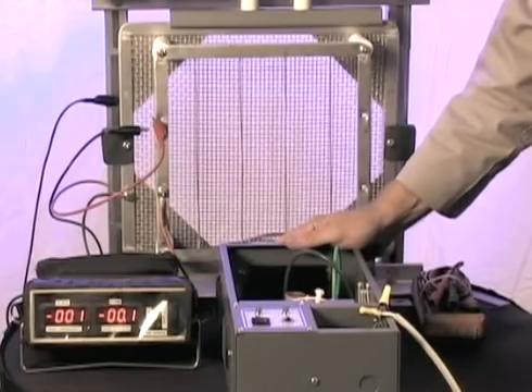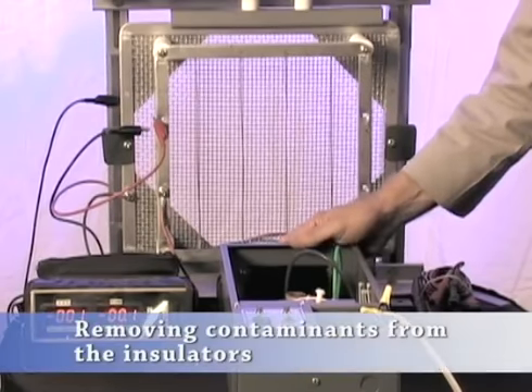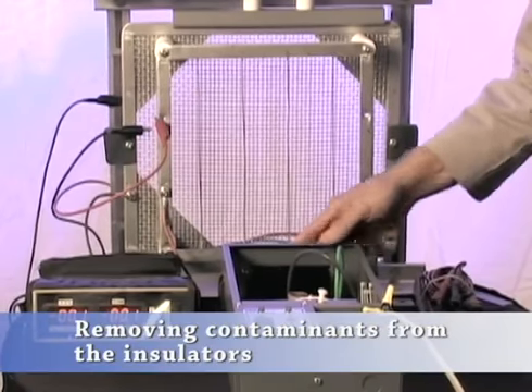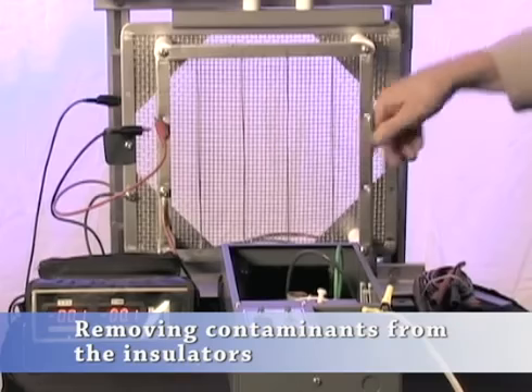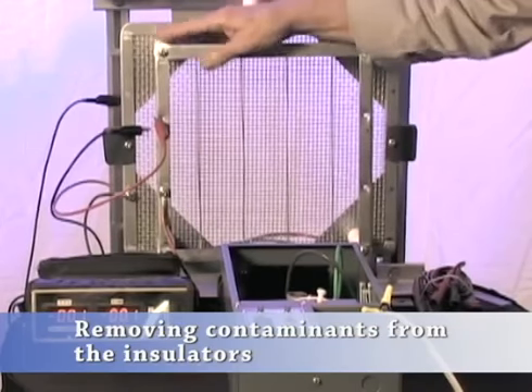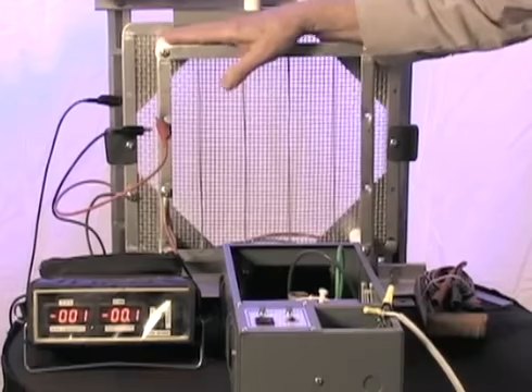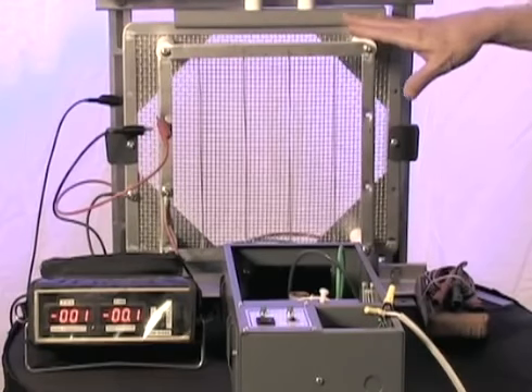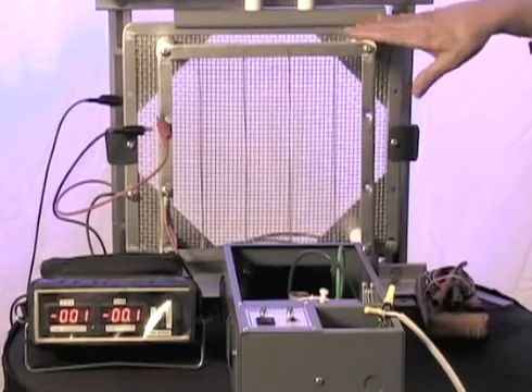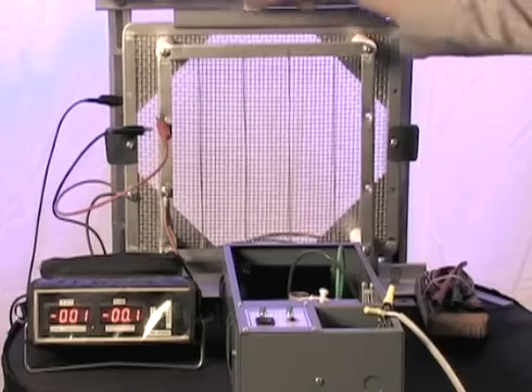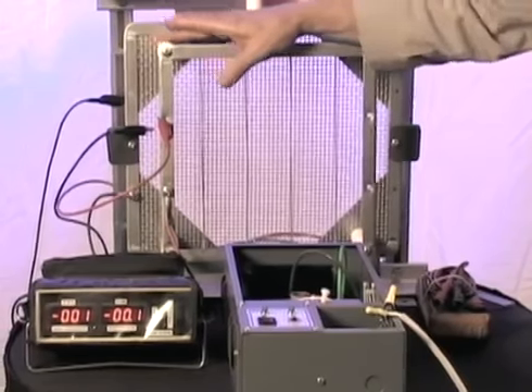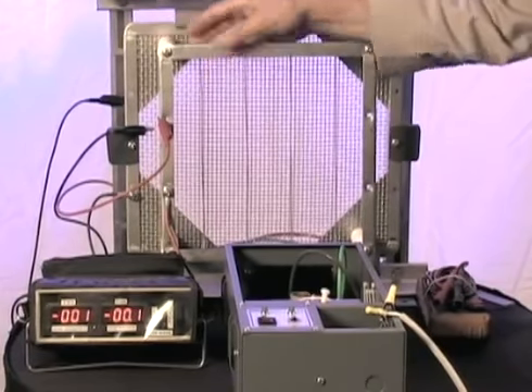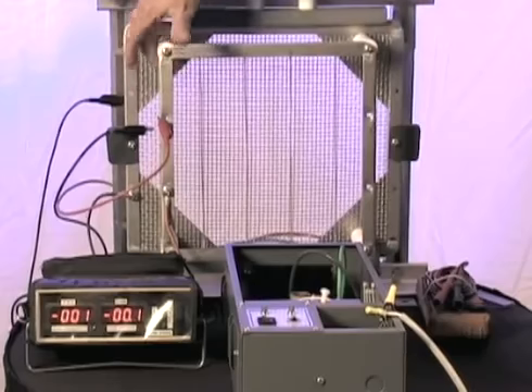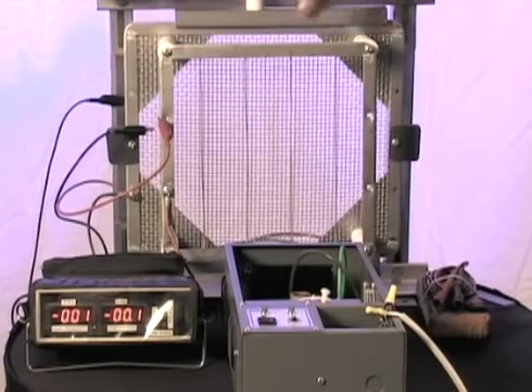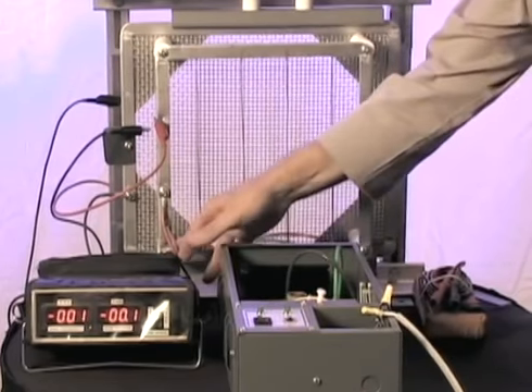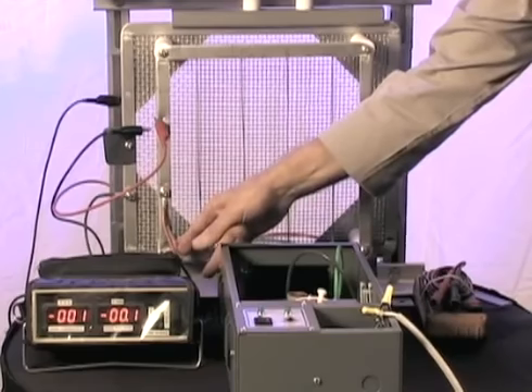If you've determined that your problems are out at the screen set, when going to the electrode set, examine the condition of the plastic surfaces of the Teflon insulators and the gray PVC track which holds the system screen set out. The insulators should be white and clean around the entire circumference of their body on all four, or if your screen has 6 of these holding it up.